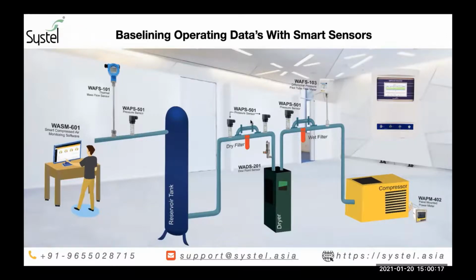And our master controller is again an artificial intelligence based controller. This controller can very tightly integrate the supply with demand. It can bring in the most efficient compressor combinations. It can control your dryers and condensate drain traps. The objective here is to achieve a low energy rate during your unloading process. You can also integrate your VFD compressors into it, and the controller can manage the VFDs in a very ideal bandwidth of 65 to 80%, which is the most efficient curve for operating a VFD compressor.